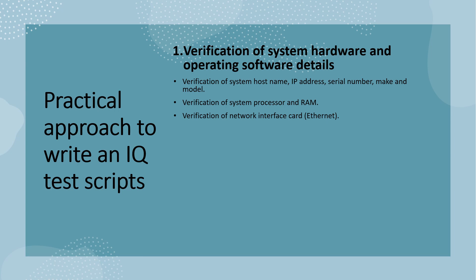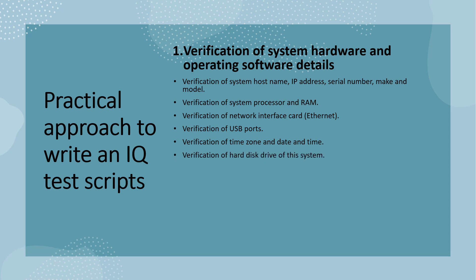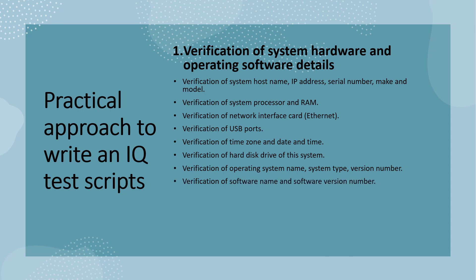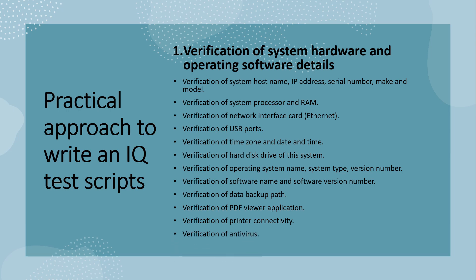Next is verification of network interface card, that is called Ethernet. Next is verification of USB ports — how many USB ports are available in the system. Next is verification of time zone as per the respective country and the current date and time. Next is verification of hard disk and its capacity. Next is verification of operating system name, type, and version number. Next is verification of software name and software version number, verification of electronic data backup path, verification of PDF viewer application, verification of printer connectivity, and verification of the antivirus installed.